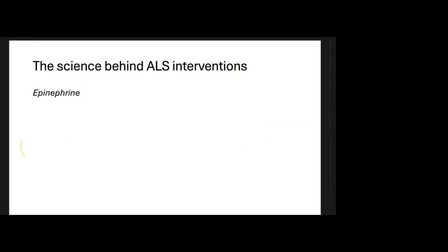Dr. Farkas, I have a question. Yes, ma'am. I'm wondering, I know in our rural setting, we most of the time carry AEDs with us. Would that be possible to do with an AED and a heart monitor? The double? Yeah, that's a good question. If it's a type of AED that you can override and set into manual mode rather than automatic, I feel like you probably could, but not every AED has the capability to do that.